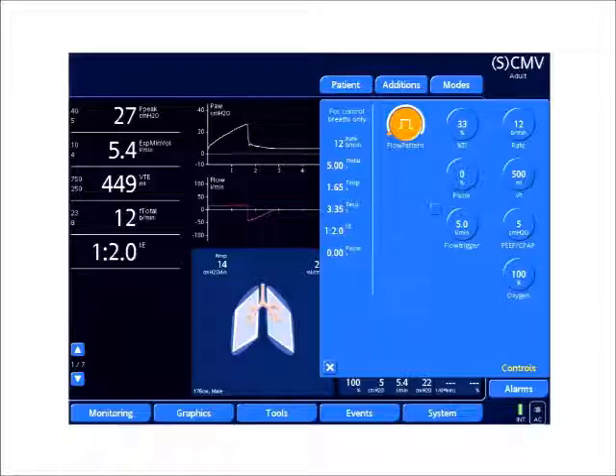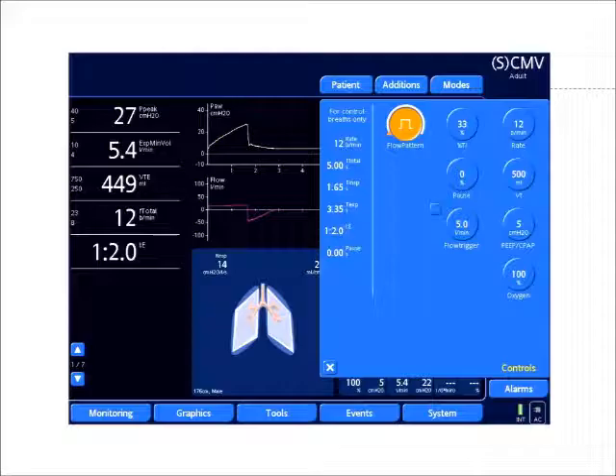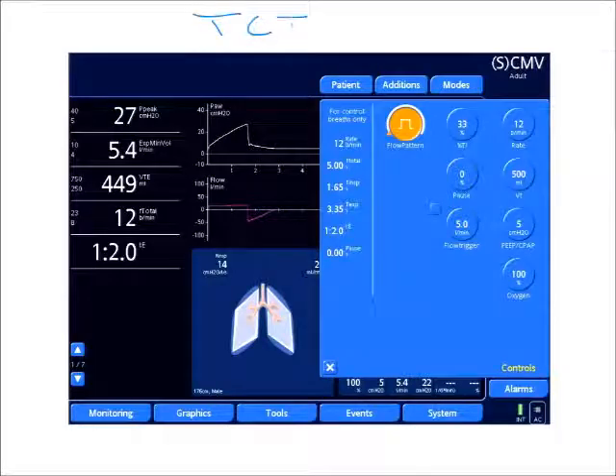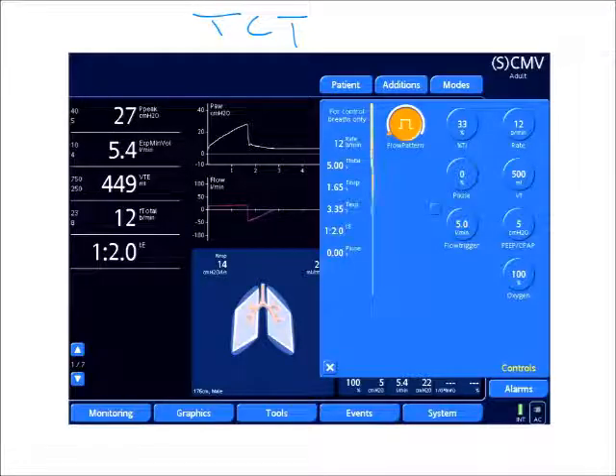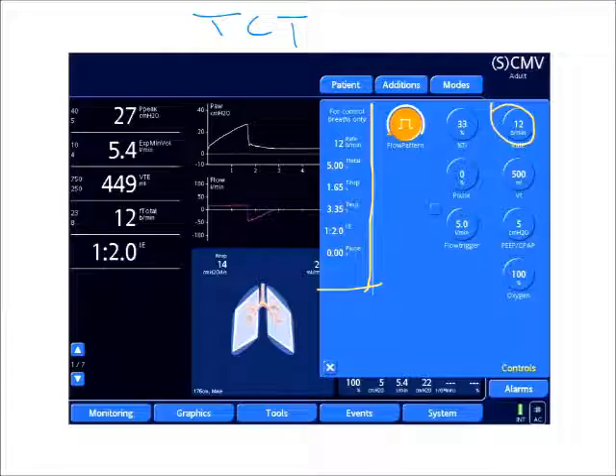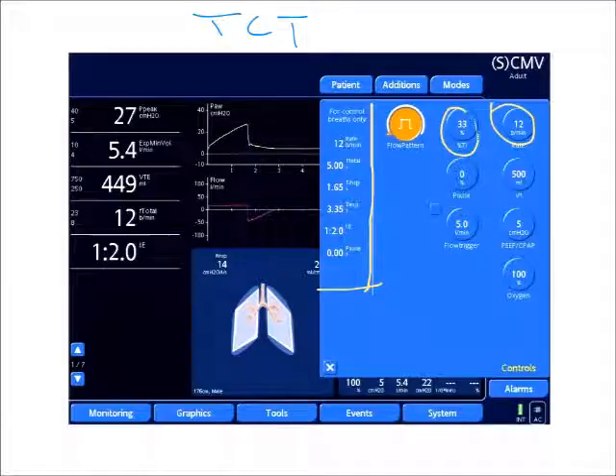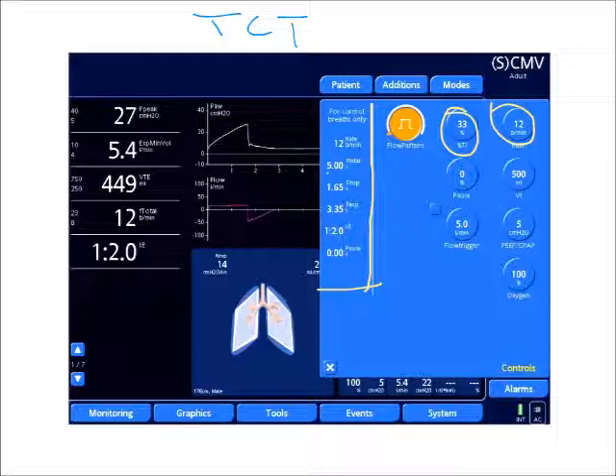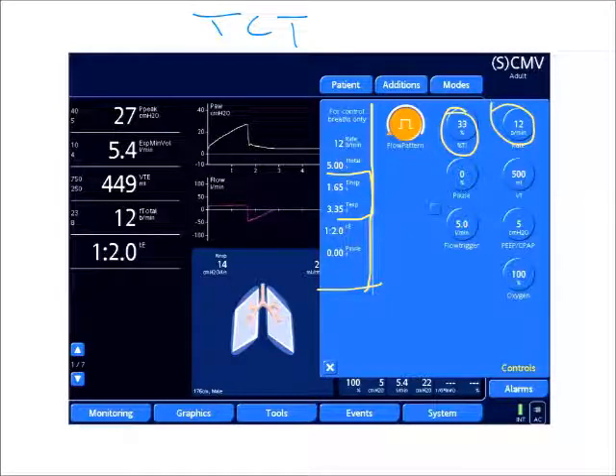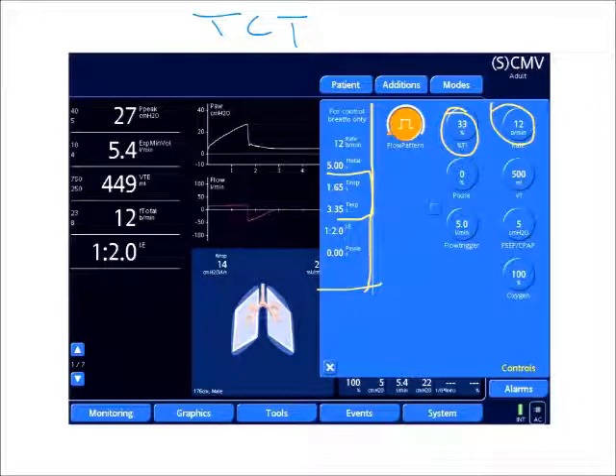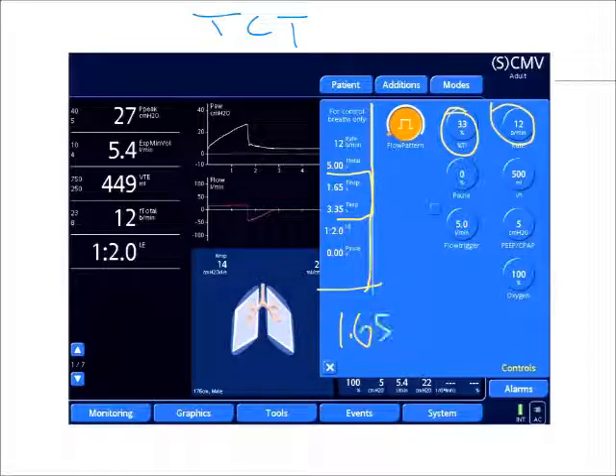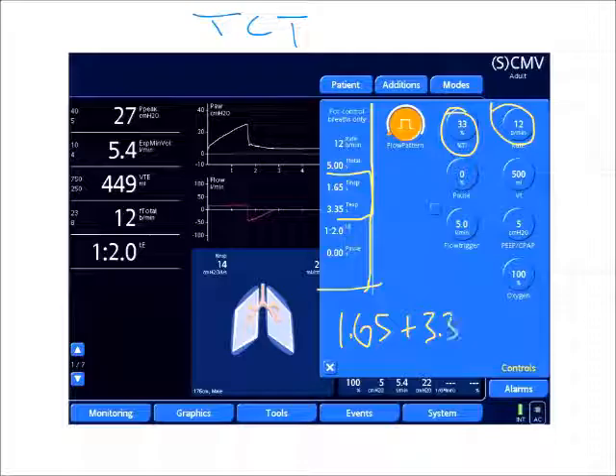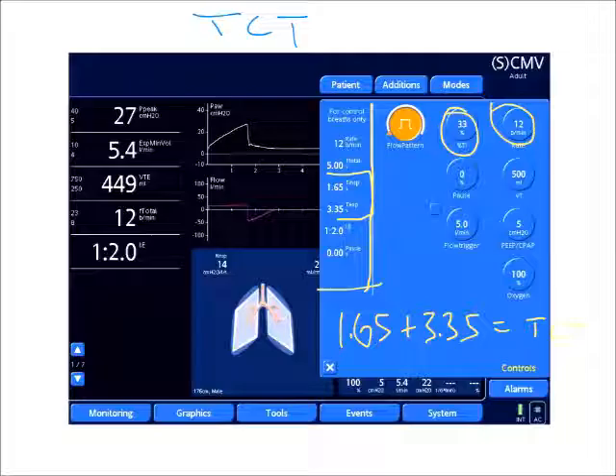Here's another example where it doesn't show my total cycle time. I don't know my total cycle time at all. However, this new ventilator also has a little smart window. Based on your settings, based on my set frequency and my inspiratory time percent, it will calculate my inspiratory and my expiratory time. Then I can calculate that. I can add those two together: 1.65 plus my 3.35, and that will equal my total cycle time.